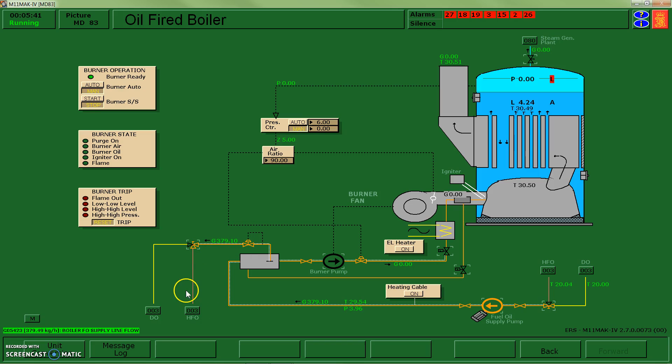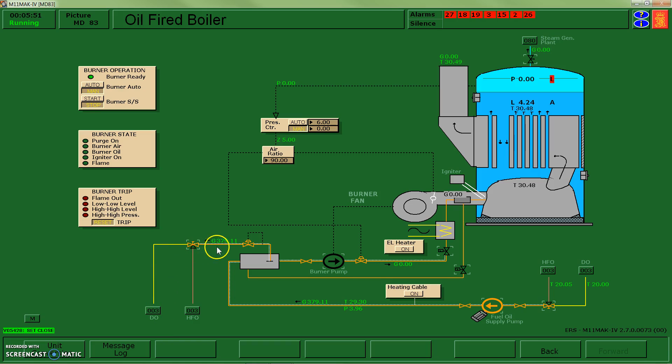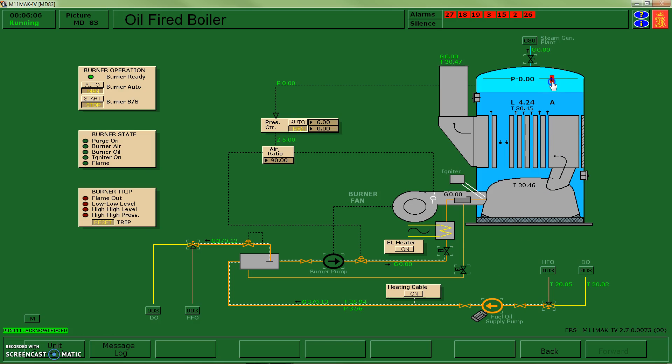Since it's going in the wrong direction here, I'm going to need to adjust that valve so that it recirculates back to my diesel oil tank. So I have a completed pathway right now. You'll notice that I had an alarm that went off, which was the pressure here. Basically as soon as I turned on that pump a few seconds later, this boiler woke up, so it's realizing now that I'm going to try and start it.